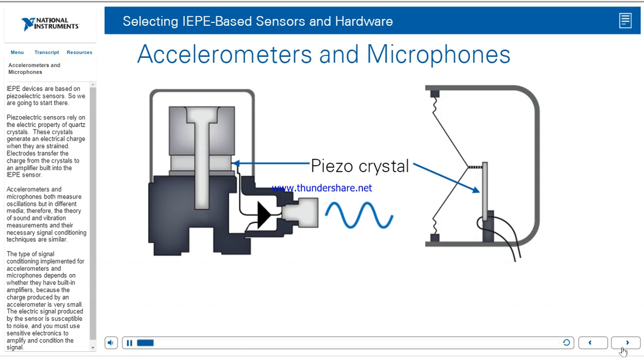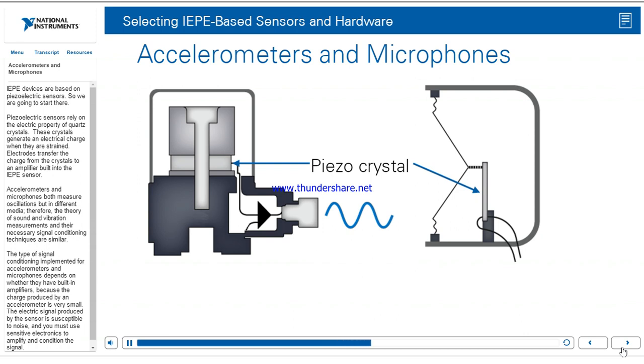IEPE devices are based on piezoelectric sensors. Piezoelectric sensors rely on the electric property of quartz crystals — these crystals generate an electrical charge when they are strained. Electrodes transfer the charge from the crystals to an amplifier built into the IEPE-based sensor. Accelerometers and microphones both measure oscillations, but in different media. Therefore, the theory of sound and vibration measurements and their necessary signal conditioning techniques are similar.